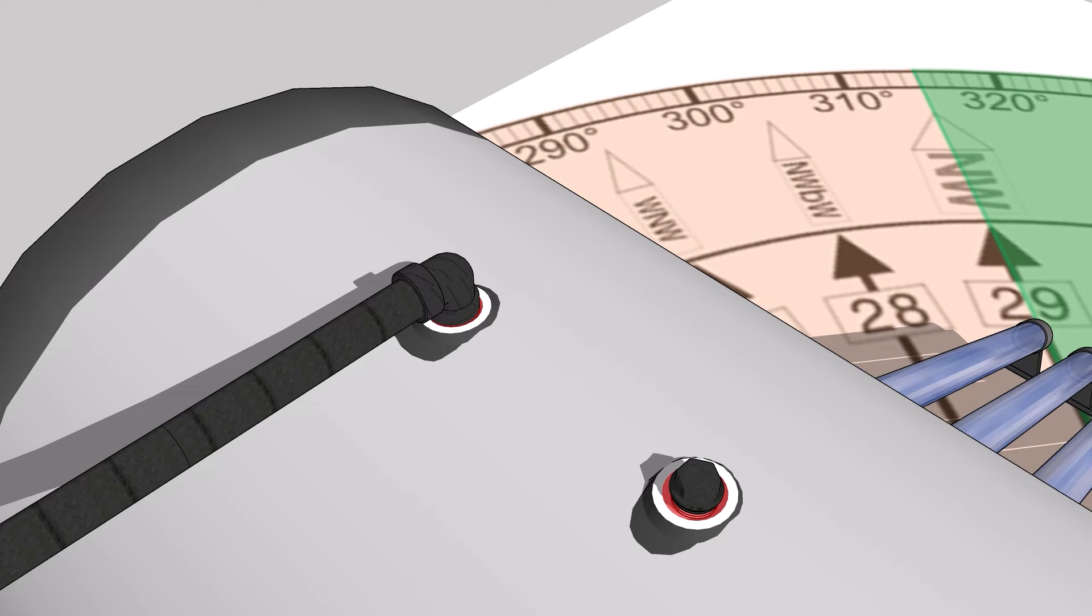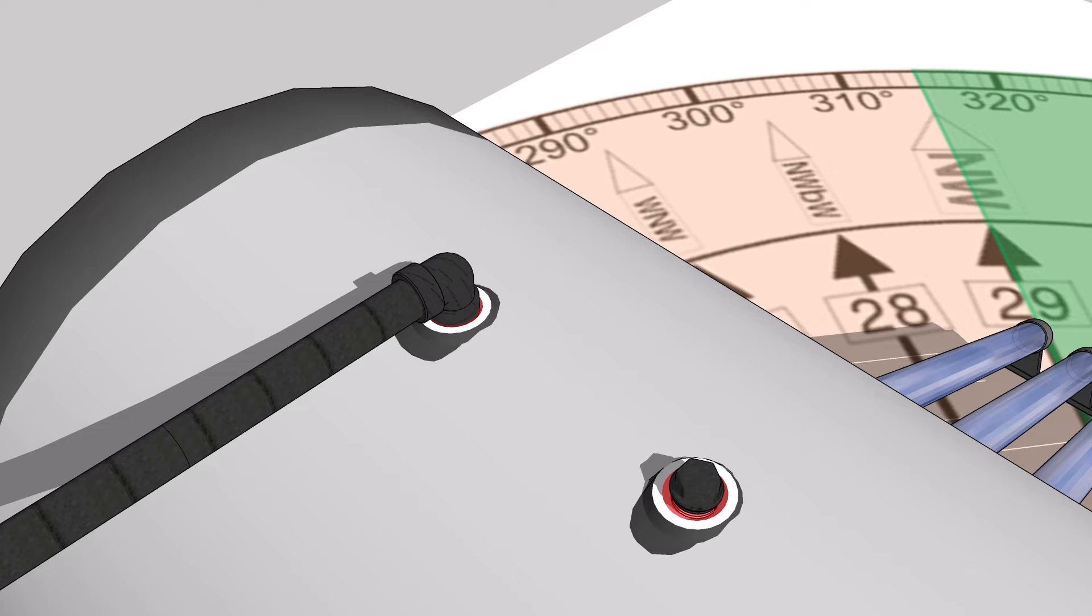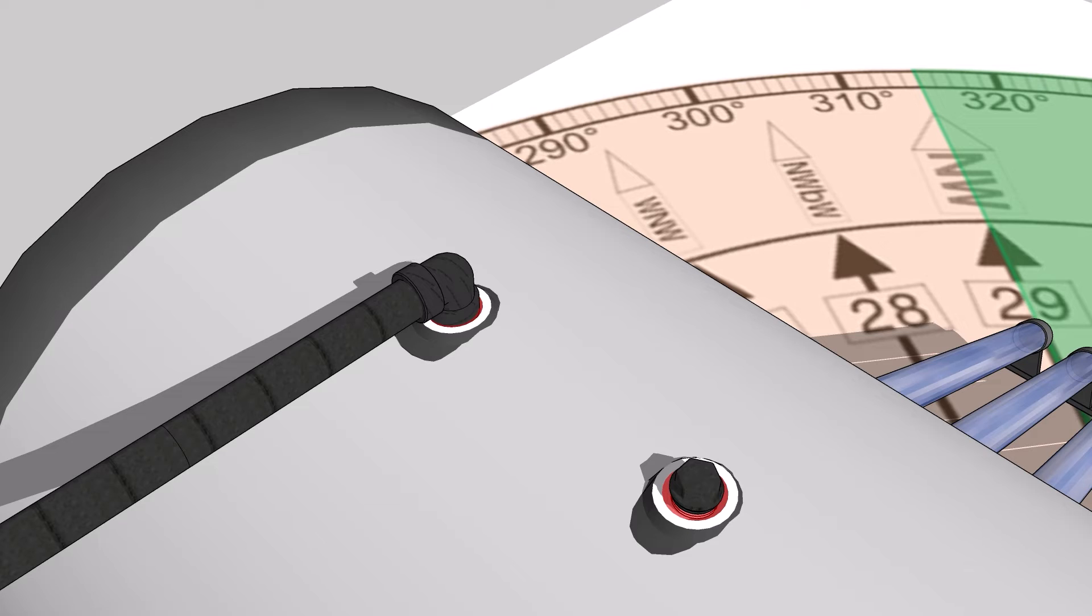A brass 22 mm male connex fitting will connect the on-roof plumbing kit to the hot water outlet. Please take note, on a 100 litre system, this will be a 15 mm male connex fitting. Take care to not install the vacuum breakers directly above the hot water outlet. Also, it is recommended to use hemp rather than PTFE tape around this thread.